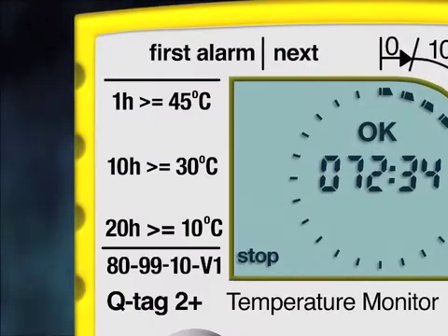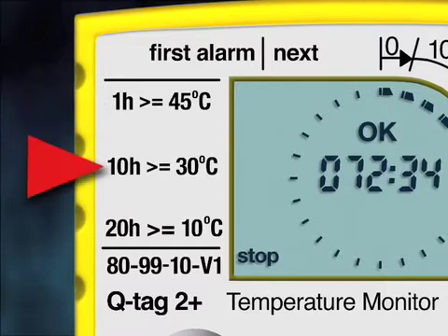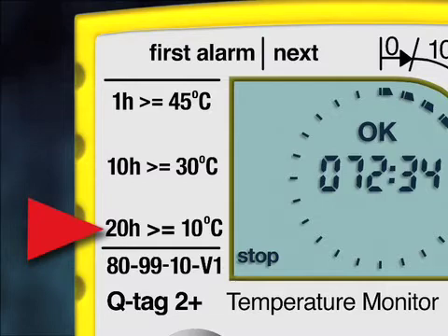In Q-tag 2+, the 45°C alarm is a single alarm activated if the package is exposed to temperatures over 45°C for at least one hour continuously. The 30°C alarm is activated when temperatures are above 30°C for at least 10 hours cumulatively. The third alarm is the 10°C alarm, triggered if exposed to temperatures higher than 10°C for at least 20 hours cumulatively.